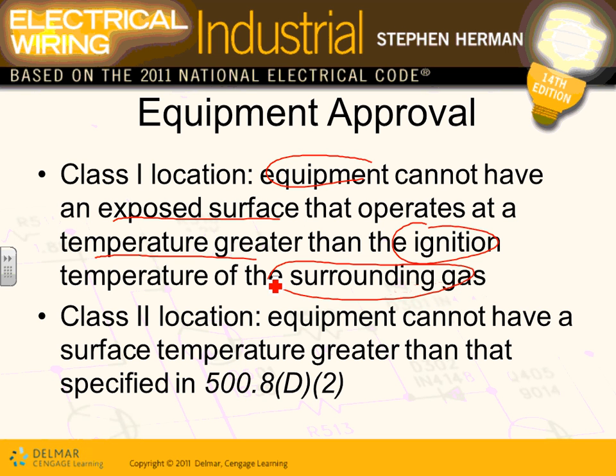Same thing for class 2 location, guys. The equipment has a temperature that's not greater than what they listed here. They have a whole table that says the equipment has to have a certain temperature based on the T rating of these equipment. So long story short, same thing in the dust. You want your equipment not to get hot enough in a dusty area to ignite the surrounding. That's it. So the equipment that they use, Derek, in a class 1 location is called explosion proof.